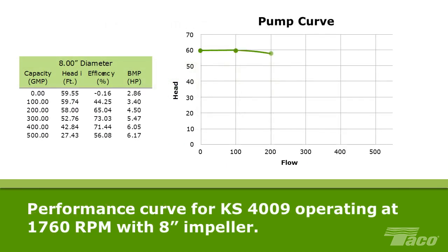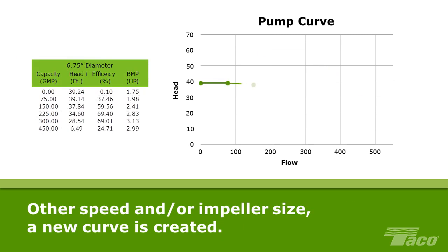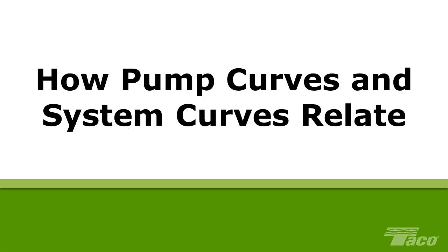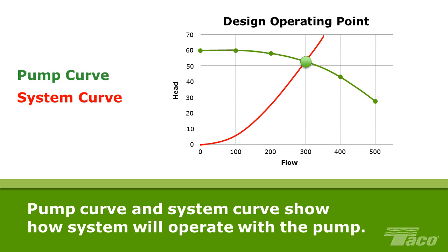This data enables us to plot a performance curve for the KS4009. The curve is accurate for the KS4009 operating at 1,760 RPM with an 8-inch impeller. At any other speed and/or impeller diameter, a new pump performance curve will be created. How pump curves and system curves relate. Pump performance curves and system curves are independent of one another.